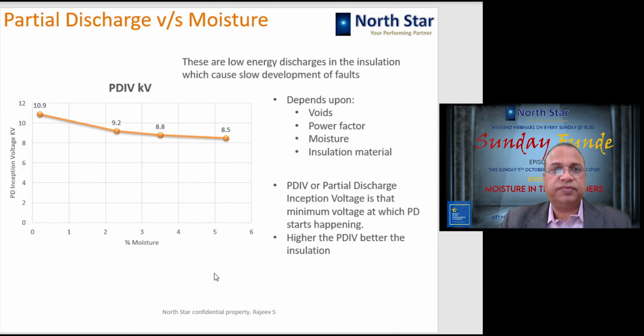Okay, what about the dielectric strength? There are two aspects of dielectric strength. One is the partial discharges which happen in the transformer due to impurities or moisture in the transformer insulation material, and the power factor or the dryness of the transformer. So partial discharges are the release of small energies into the insulation because of these factors, and these energy discharges slowly damage the insulation, and then when some surge or impulse comes, the damage which has happened because of partial discharge gets supported by these electrical surges, and then the insulation fails.